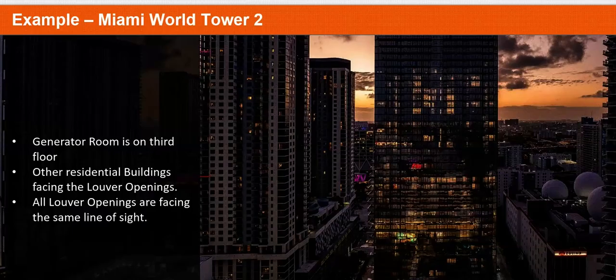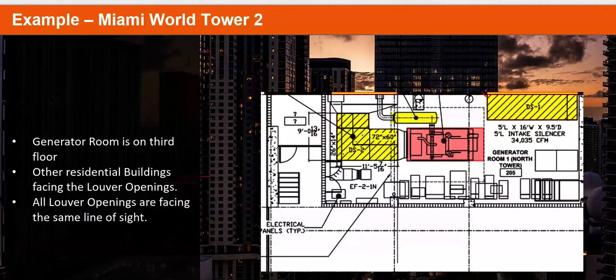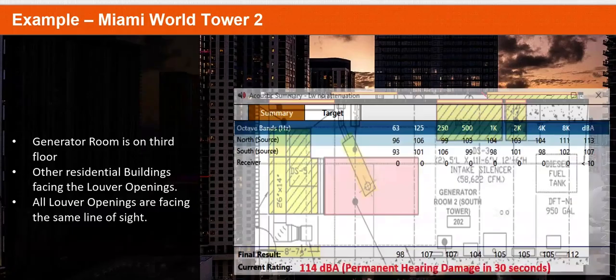The placement of this new building is obviously in a very crowded city with luxury buildings with balconies around. And what we advised for was an elbow silencer to get extra length on the radiator exhaust, and a 4 to 5 foot long inlet silencer so that these generators could operate, especially because they test them about twice a week for half an hour. If you think about this specific job, it's on the 3rd floor and you're shooting 100 plus decibels or 114 decibels towards balconies, it could be very detrimental to the human ear.